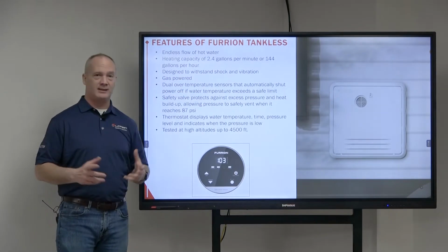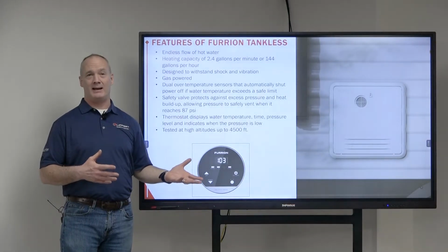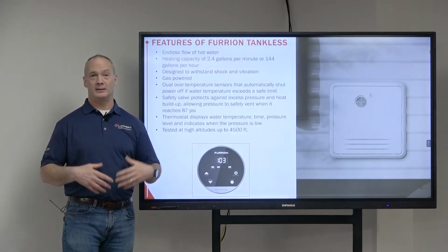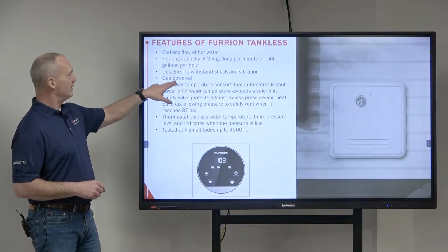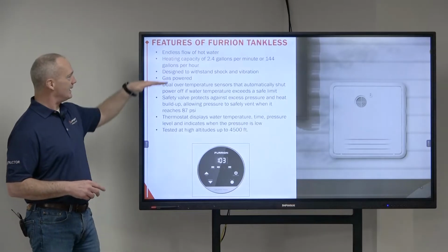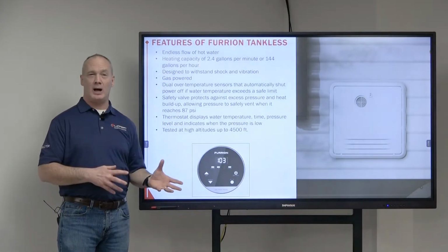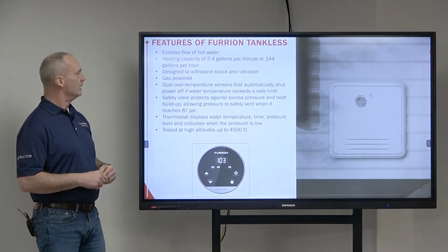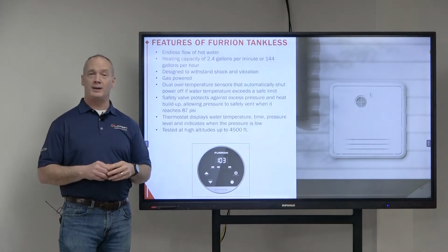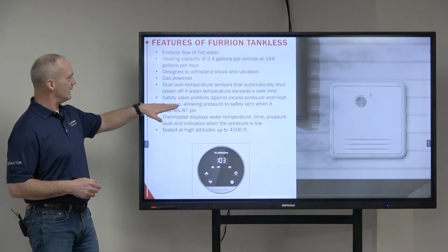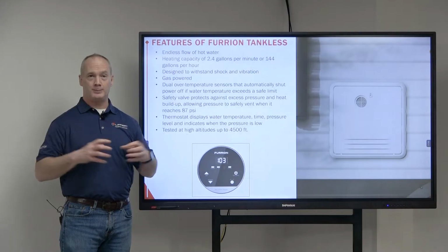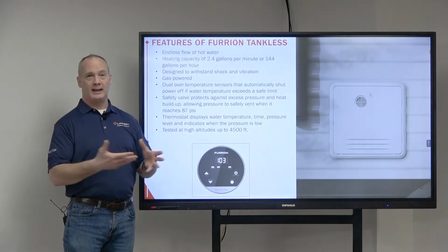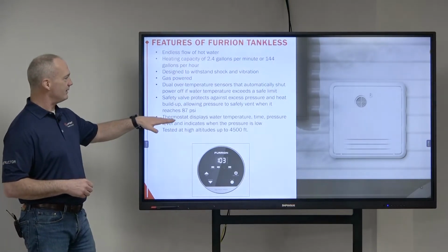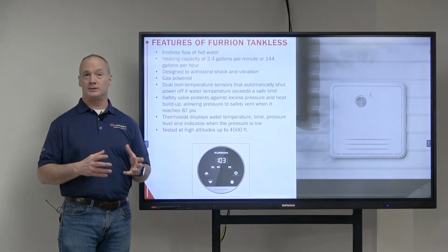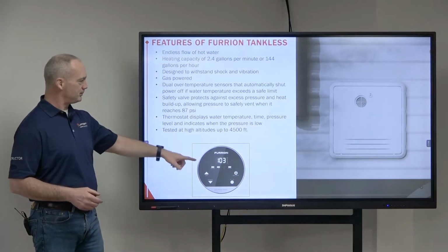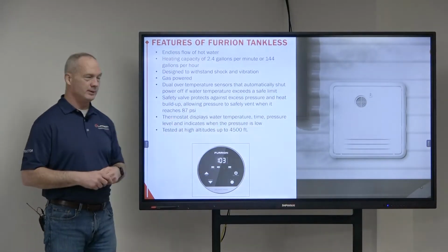And it's designed to withstand shock and vibration because the water heater in your basement, well, that doesn't need to have that kind of feature to it. Well, they do in an RV because you're going up and down those bumpy roads. This tankless water heater is gas powered and has several safety features built into it so it doesn't get too hot or build up too much pressure. So you have dual over temperature sensors that will automatically shut down the water heater if it gets too hot. And it also has a safety valve that protects against too much pressure buildup. So if it gets too hot and the pressure builds up, it releases that pressure through the safety valve. Now it does have a thermostat that you can put anywhere inside the coach that you deem convenient for you, and it will display the temperature, time, pressure, and indicates when the pressure is too low.